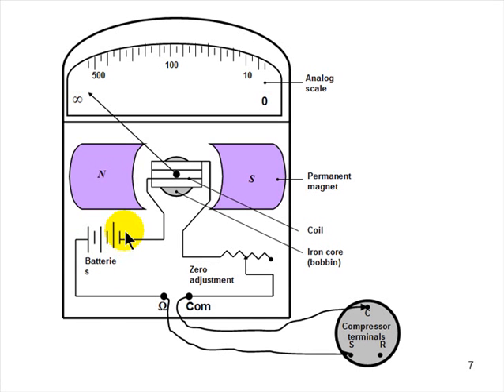Now, a good meter in this circuit somewhere will have a fuse so that when you do make the mistake of applying 24 volts to a 4.5 volt circuit, you don't smoke all the wire and destroy the internals of the meter. A cheap meter is what we call disposable. It doesn't have a fuse, and when you put 24 volts or, God forbid, line voltage across a 4.5 volt circuit, you just let the smoke out of it. And when you let the smoke out of something, it doesn't work anymore. If you can keep the smoke in, it'll work. The same with motors. Very true.